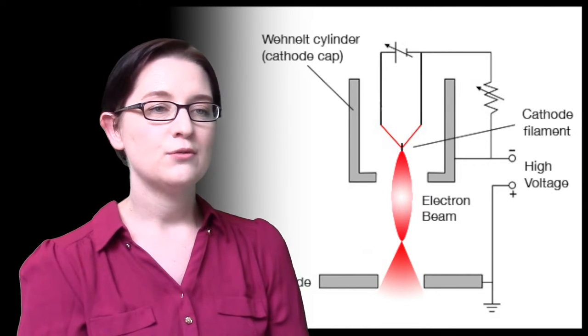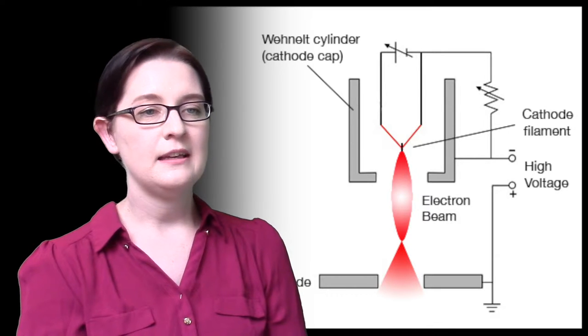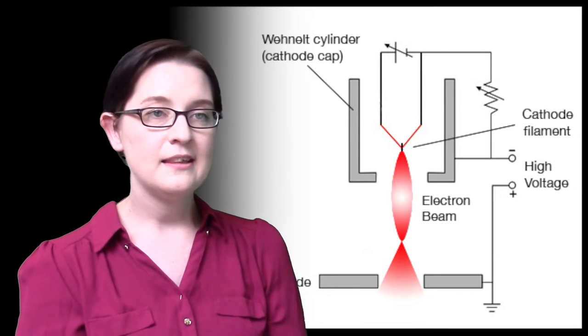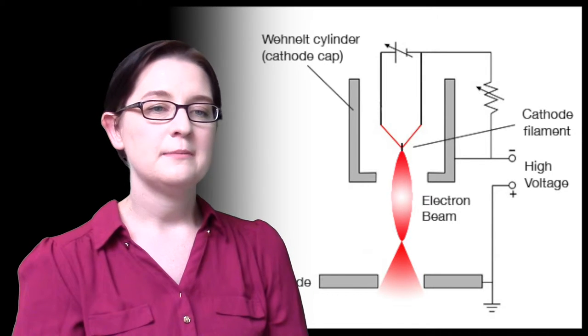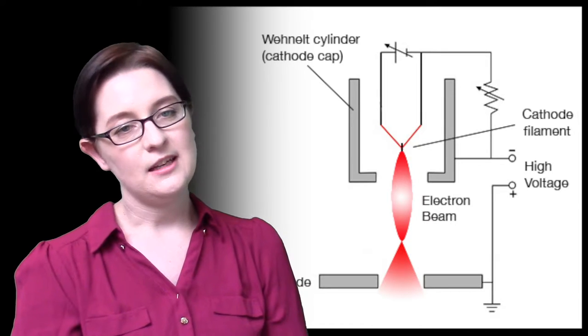This high tension (HT) controls the accelerating voltage of the emitted electrons. The higher the accelerating voltage, the higher the resolution, but there is a greater chance of specimen damage plus a reduction in contrast.